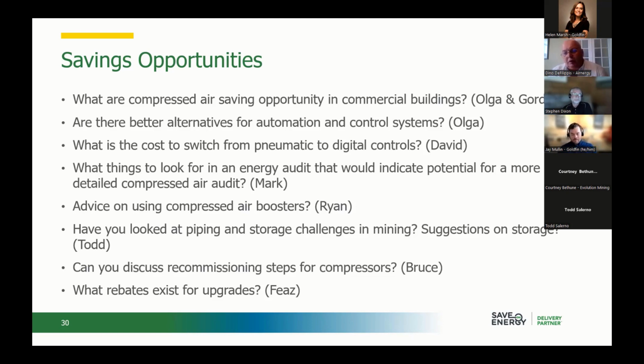I know of a few customers with water-cooled compressors, and some that we've upgraded from air to water-cooled. They've used the discharge off the heat exchangers. One was a food plant where they ran the hot water out of the heat exchanger to pre-warm water for some processes and kettles. Another used it for warming up their boiler feed water, going from the discharge of the heat exchangers to boiler feed water through another heat exchanger, which reduced the load on their chiller system and closed loop system.